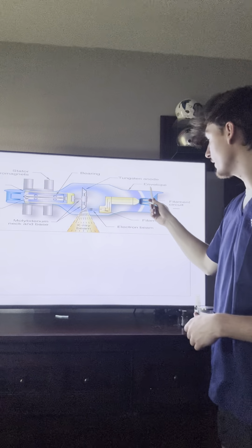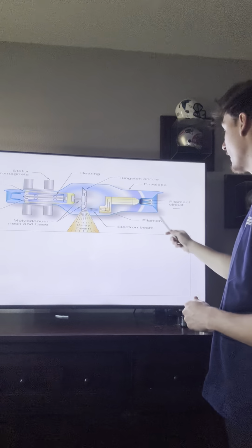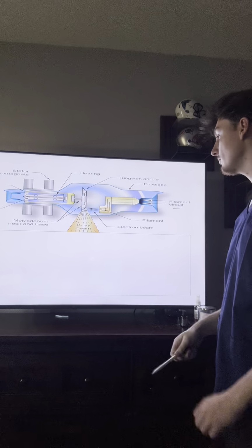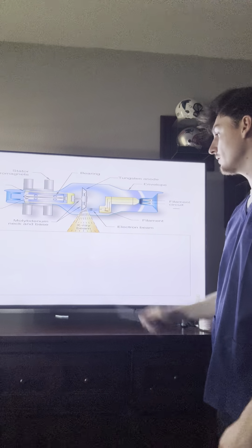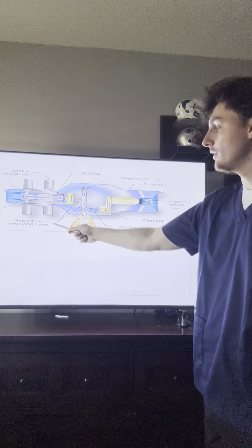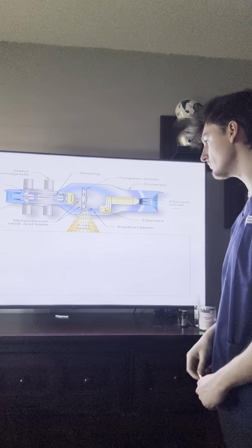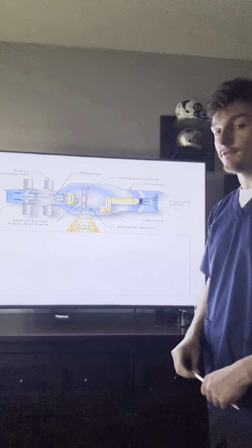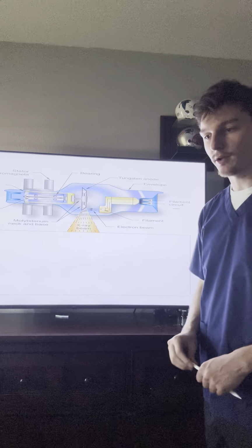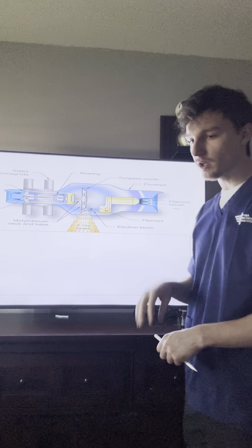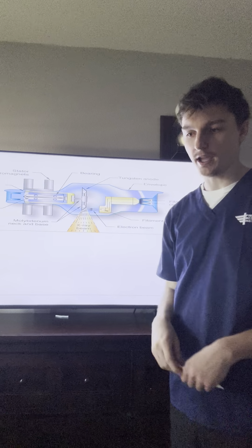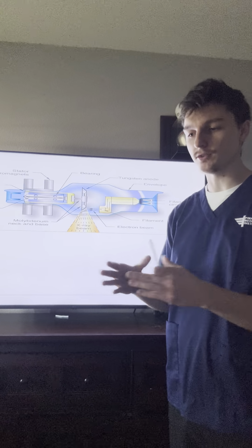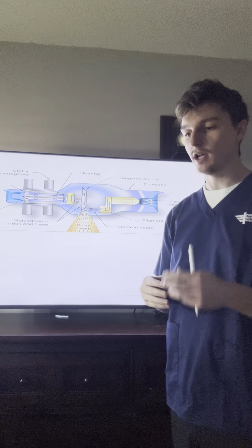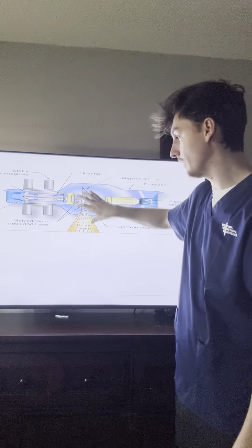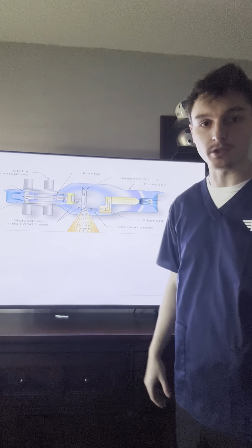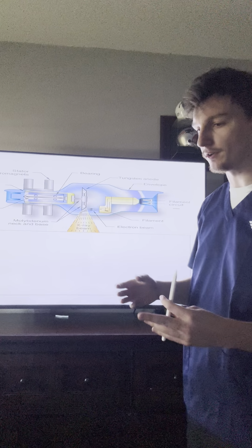Now we have our envelope right here. We're going to have our wiring for the filament circuit and the filament right here. And we're going to have the electron beam here. We have the molybdenum neck and base right here. And then we're going to have our nickel focusing cup as well. And that tungsten high heat and nickel will be used hand in hand because it has low negative potential, and it helps that electron beam work, which is what we need and what we want, which is very important here.